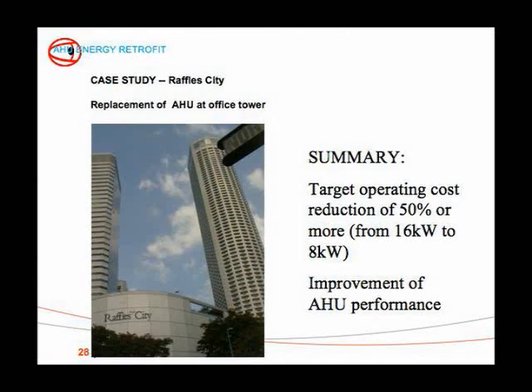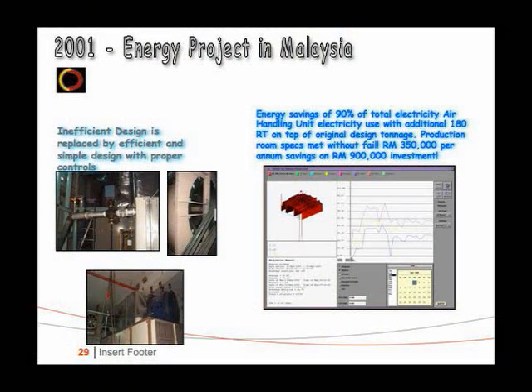Commercial buildings. This is a very tall office building, Raffles City. Somebody in New York, I'm not picking on New York, you know, the good guys. Somebody designed the air handlers. Obviously, system efficiency was not a consideration. So we went in and did a 50% change out. Potential for savings is very high because of running hours and larger air volumes. This is a semiconductor plant, 90% savings on the air side.